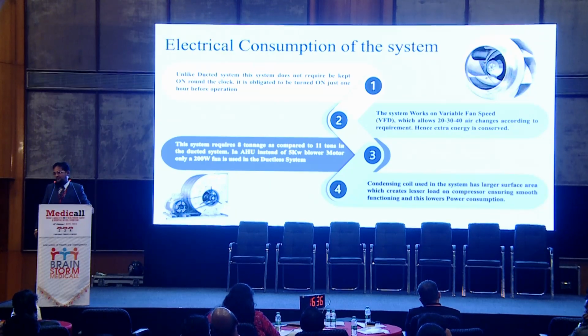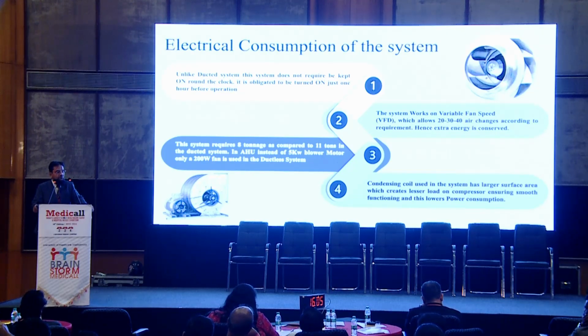So preparation time will be less. You don't have to wait. Before starting, you can start with 40 air changes, and once your patient is in, you can take it to 20 air changes. Another thing is that at a particular time you require lower temperature. For example, at the time of cementing, you require 16 degrees. To bring down that temperature immediately, if you put it on 40 air changes, the air flow will be fast, so cooling will be achieved very fast. This is another benefit.